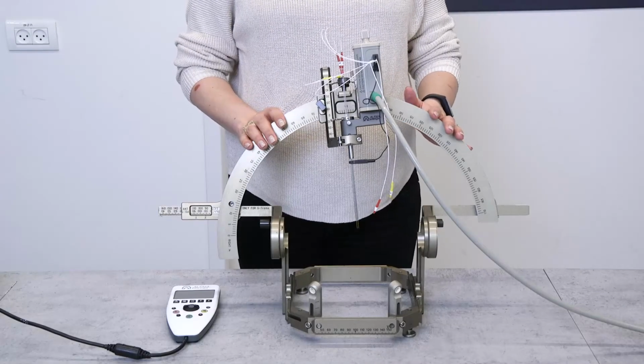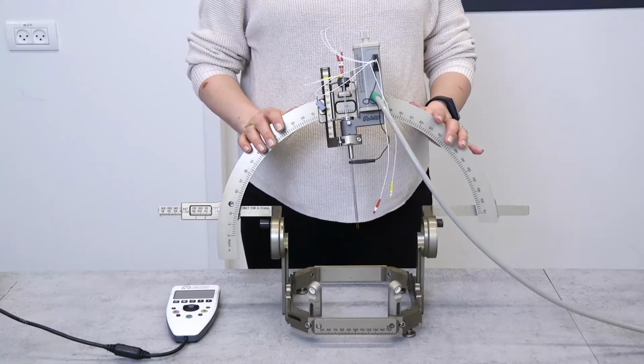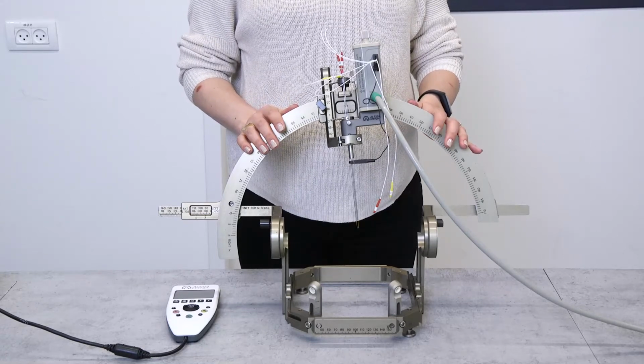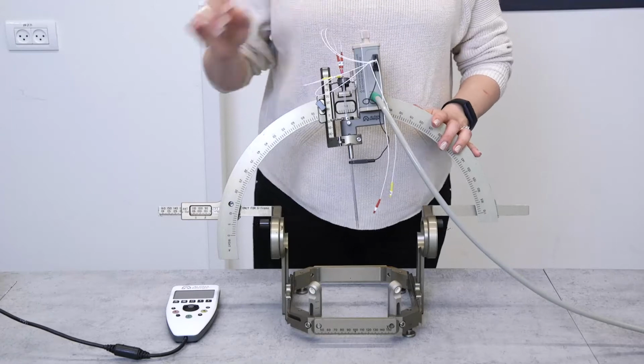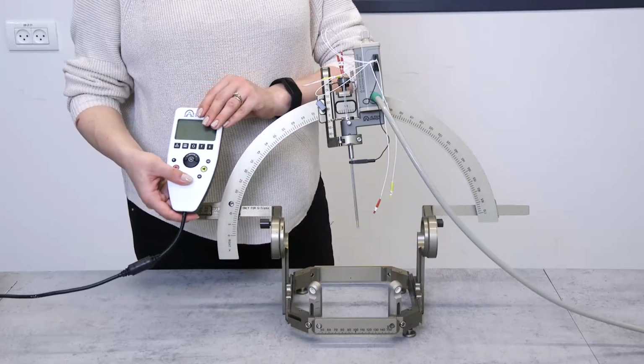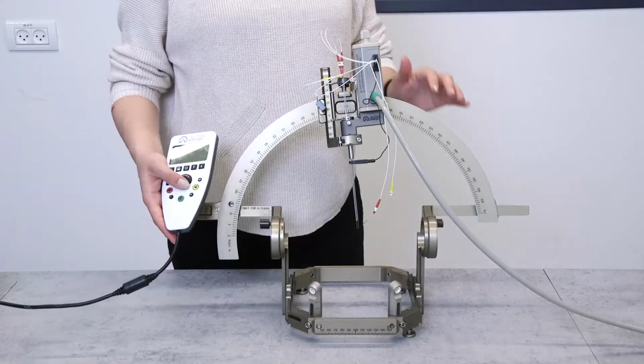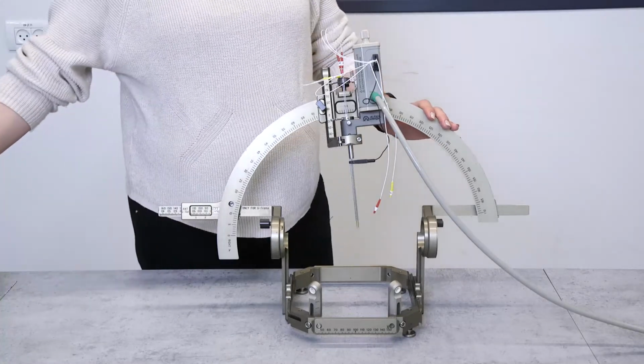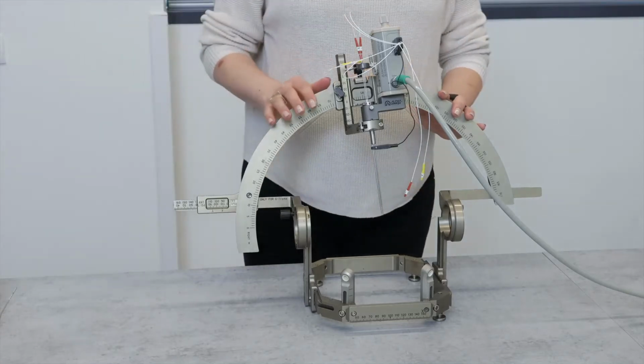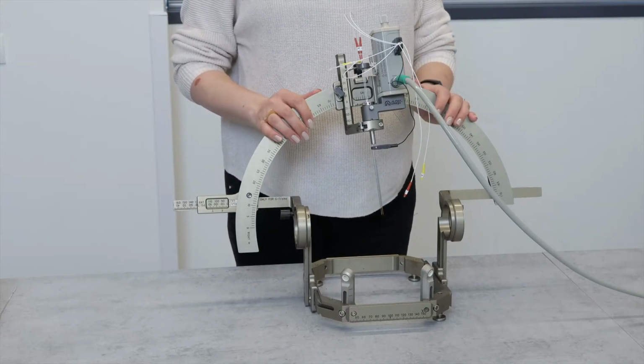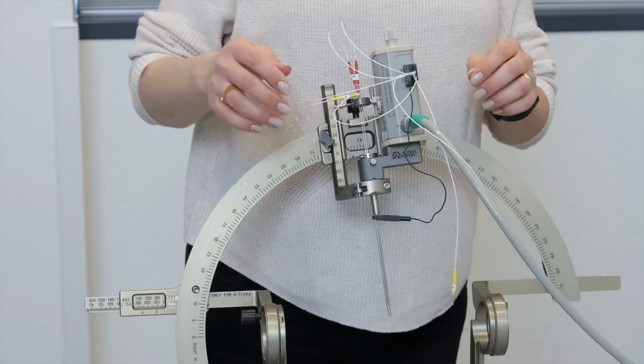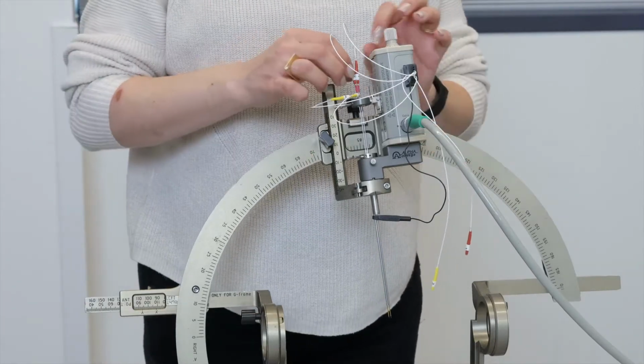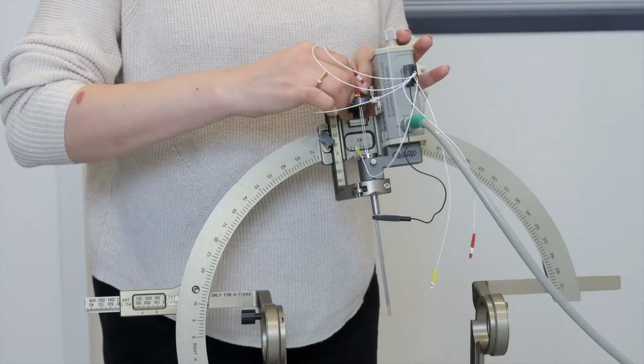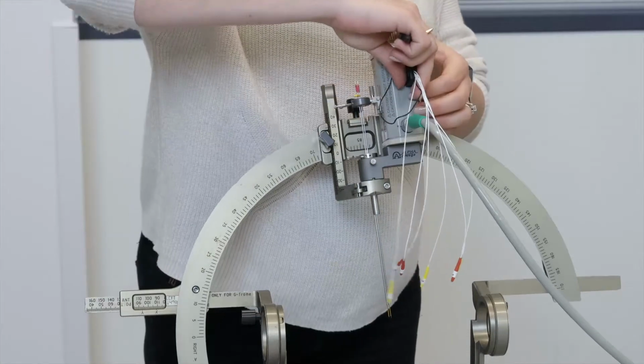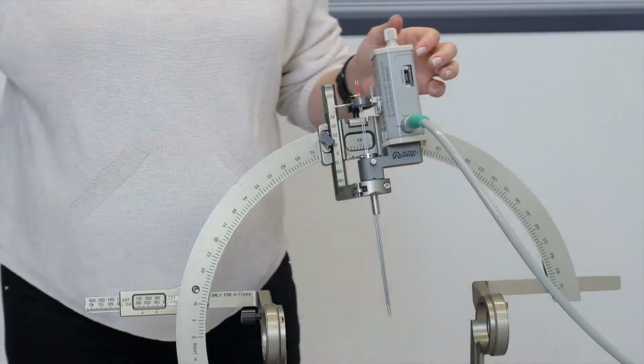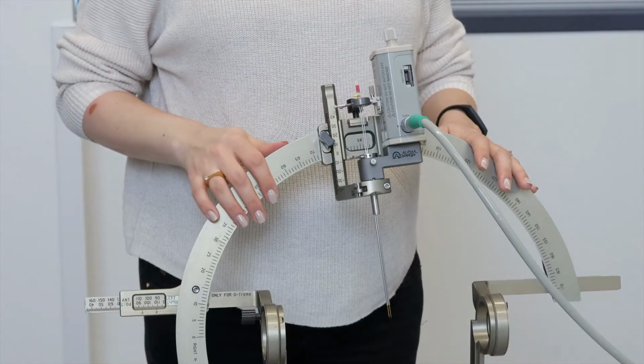Once done with the MER and have identified the desired trajectory for implantation, move the macro tip of the neuroprobe to the desired implantation depth using the drive's knob, the smart button, or the wheel on the remote control, or the software on your MER system. For verification purposes, some of our healthcare providers take a picture using fluoroscopy or O-arm. Disconnect the input cable. Remove all electrodes and the electrode holder.